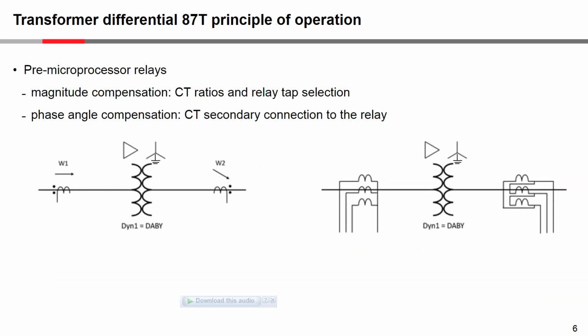So we're going to start off and look at pre-microprocessor-based relays, and we're going to look at the magnitude compensation and the phase angle compensation. Considering first the magnitude compensation, this was really done by CT ratios. The CT ratios were chosen to give us best matching secondary currents, and for what the CT ratios couldn't do, we had the relay tap selections. And the phase angle compensation was primarily achieved by the CT secondary connection to the relay.